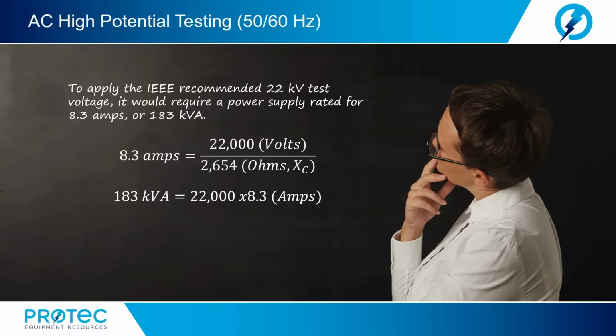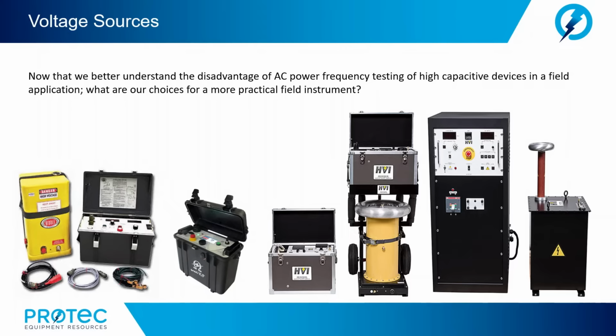In order to find VA, again, we just simply take the 22,000 volts, multiply it by the 8.3 amps, and we see that the transformer of our power supply would need to be 183 kVA in order to energize that 1 microfarad of capacitance up to 22 kV at power frequency. Somewhat large test set. Okay, now that we better understand the disadvantage of AC power frequency testing of high capacitive devices in a field application, what are our choices for a more practical field instrument?